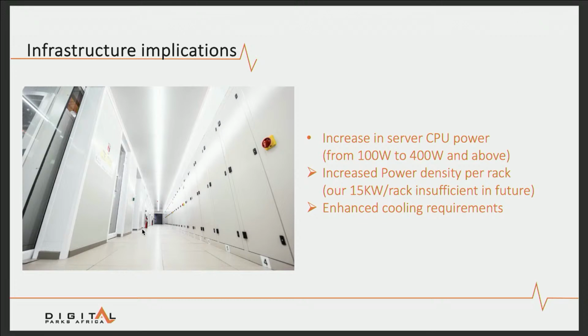Overall, putting a few of these servers in a rack, traditional data centers started out maybe with 3, 4, 5 kilowatts per rack. We've had implementations of up to 15, 20 kilowatts a rack, but we can already see that air cooling is going to reach its limitation in terms of what it's able to cool. So for us, it's becoming all about enhanced cooling requirements.